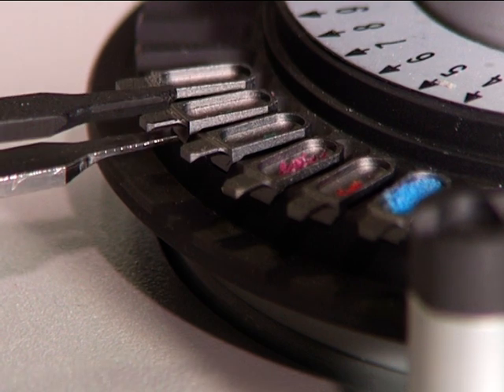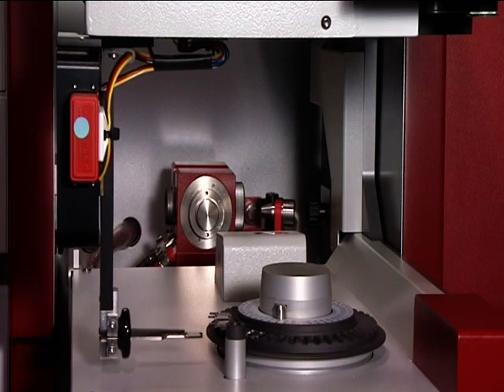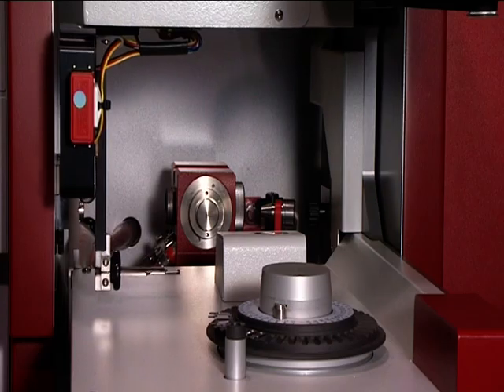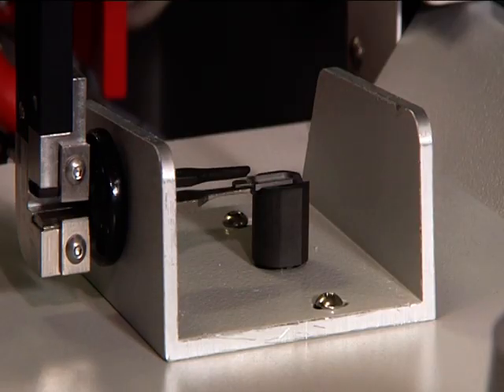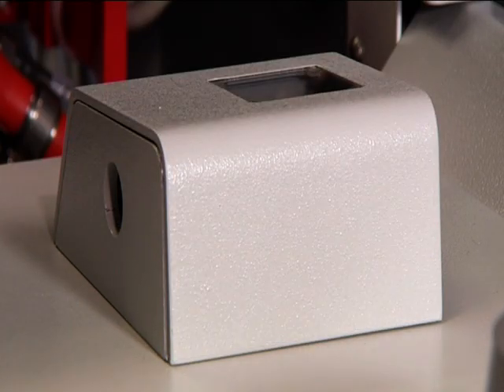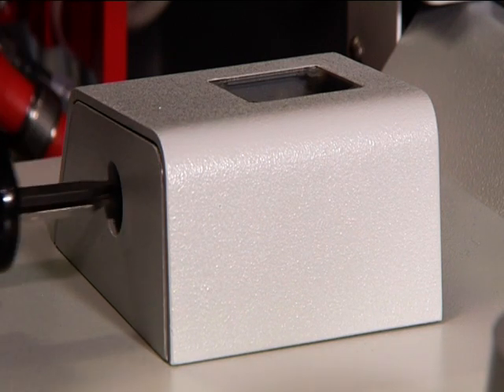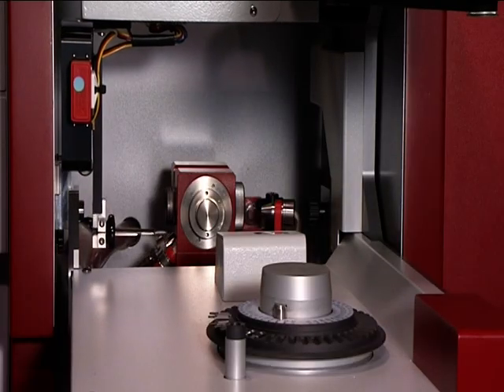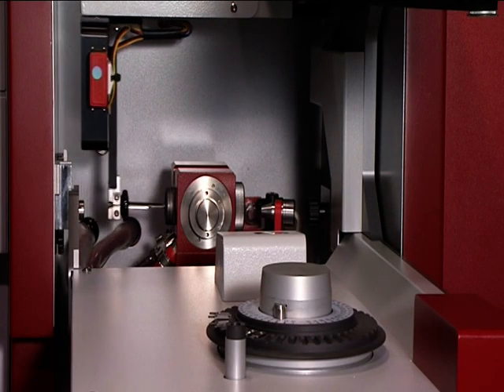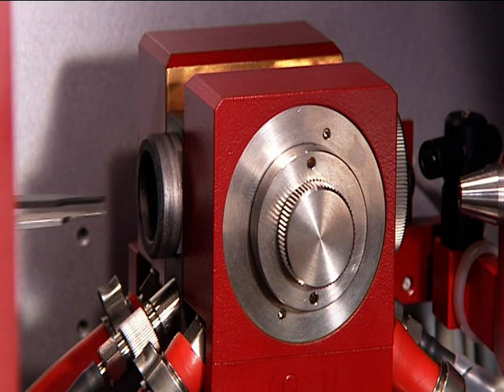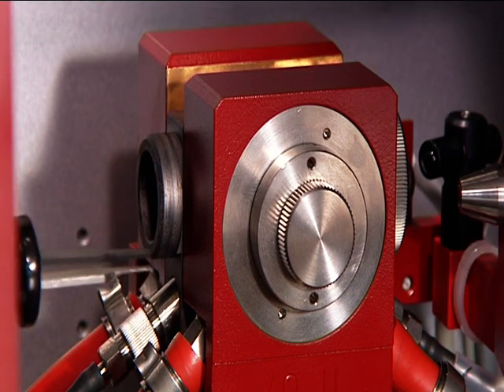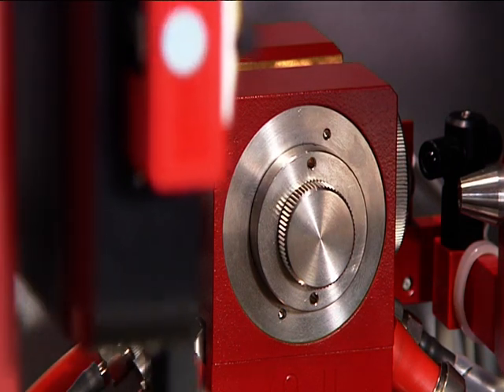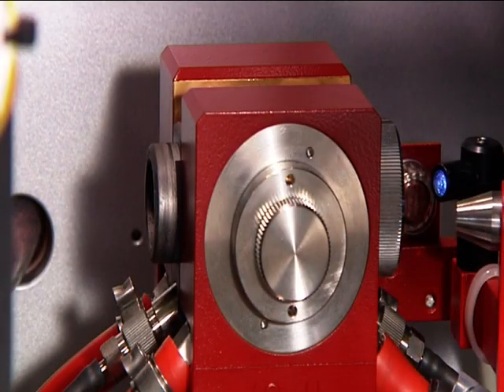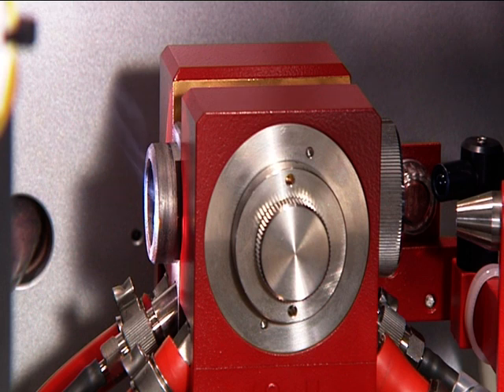Equipped with the automated solid sampler, the ContraAA opens up new ways of analyzing solid samples. The time-consuming sample preparation and the danger of contamination and loss of material to be analyzed are reduced to a minimum. The sample only has to be comminuted and optionally homogenized and can then be analyzed directly. The advantages of higher resolution and spectral information are also shown here. The additional information content, as well as the correction possibilities of the ContraAA technique, are valuable aids in method development.